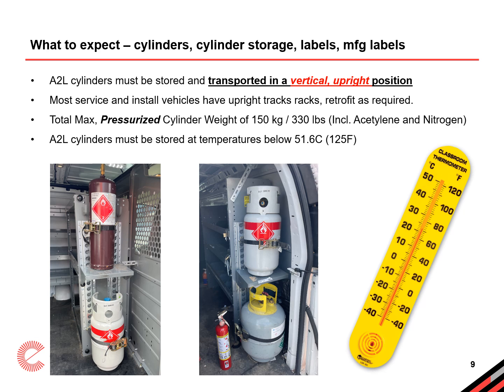Temperature control is also crucial. A2L cylinders must be stored at temperatures below 51.6 degrees Celsius or 125 degrees Fahrenheit. This is not just a guideline, it's a safety mandate. Temperatures above this limit can increase the pressure in the cylinder, creating unnecessary risks.